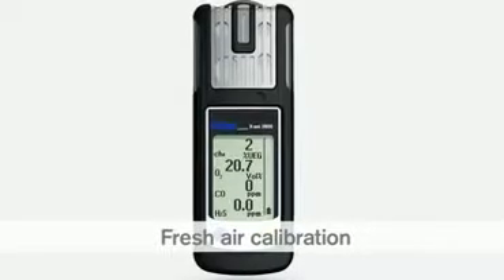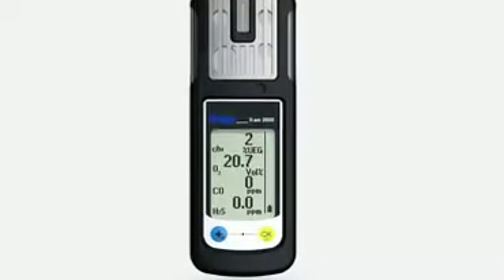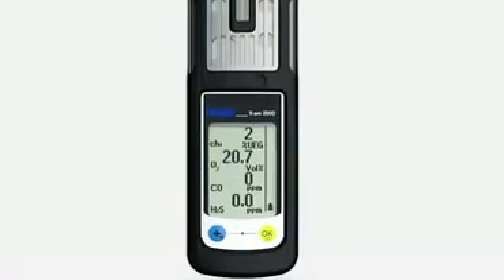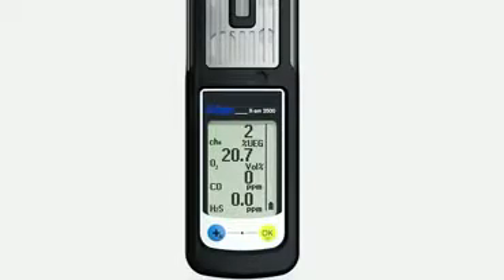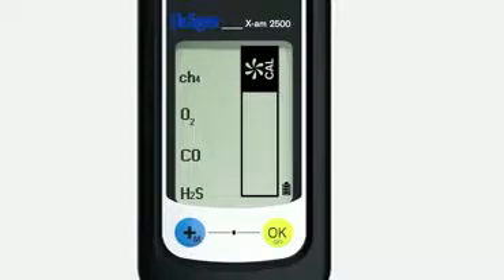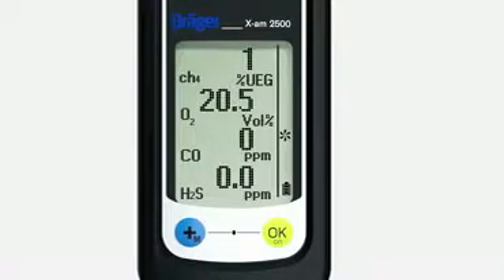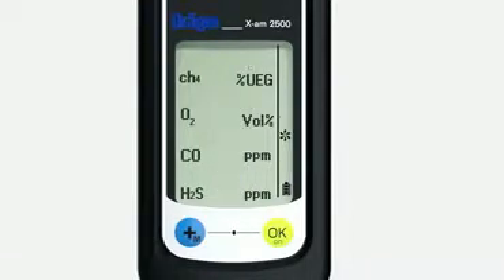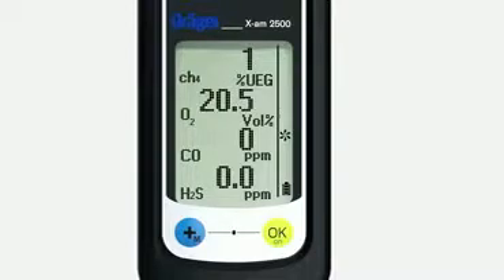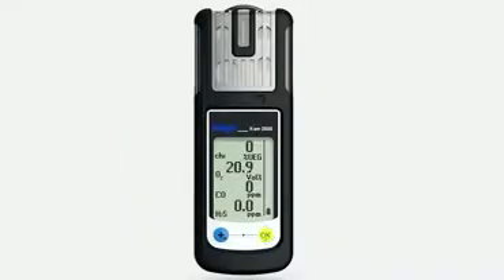Fresh air calibration sets the oxygen channel to 20.9% by volume and the sensors to 0. Make sure you are in an area of clean air during fresh air calibration. Press the plus key briefly 3 times. This symbol appears. Press the OK key to activate fresh air calibration. The flashing numbers show the actual values. Press the OK key. OK is shown in the display. Fresh air calibration is now complete.